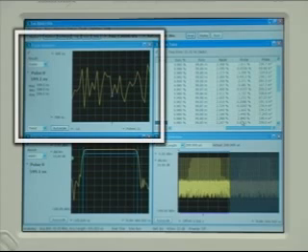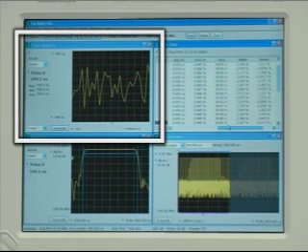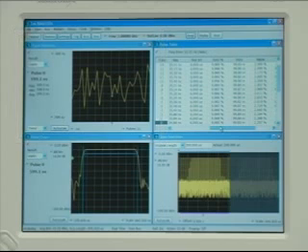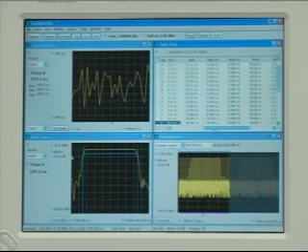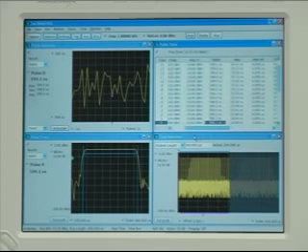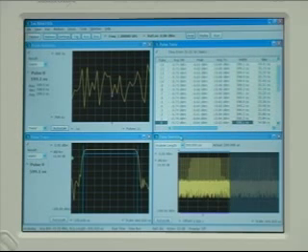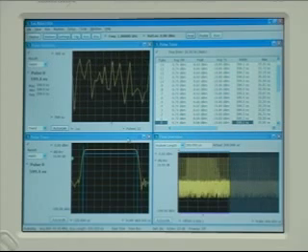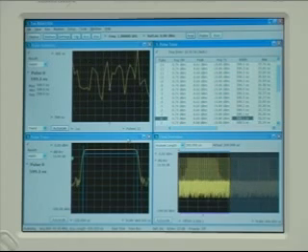The upper left display shows the trend of results of a single pulse parameter for the complete pulse train. Looking at the results across the complete pulse train or just a portion of the pulse train enables the engineer to quickly analyze how the pulse parameters are varying over time.